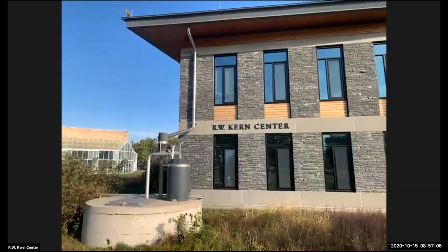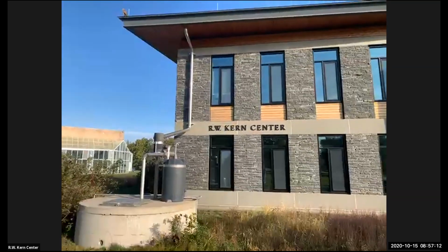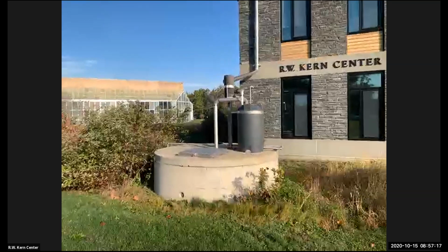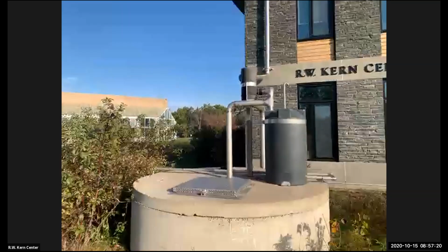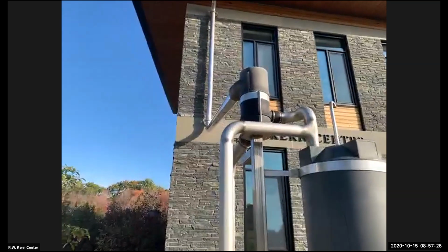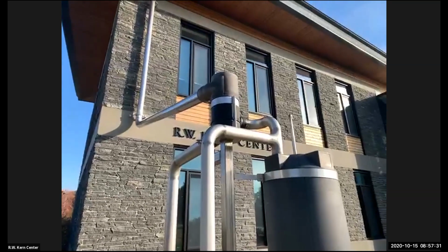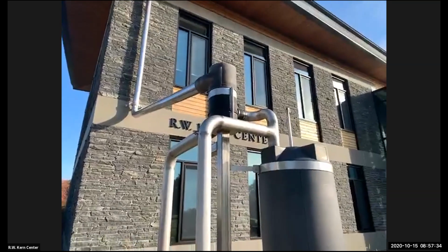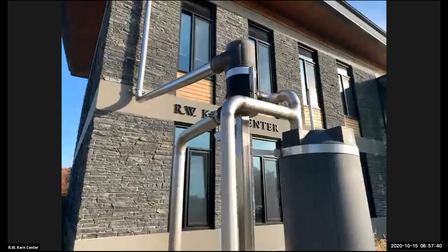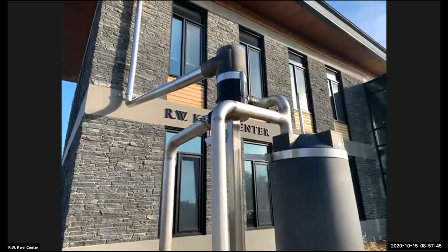So as we talked about, the water comes off the roof in that downspout. The first place it goes is that small black cylinder that you can see at the top, which we call a WISY filter. WISY, W-I-S-Y, is a brand name, but this is a vortex screen. If Claire can move just a little bit to the left, you can see that the downspout comes in eccentrically, and through inertia, when it's raining nice and hard, the water tries to spin around the outside of that cylinder. In there, we've got a stainless steel basket that screens out the debris and leaves and any other big chunks of anything, like owl poop.